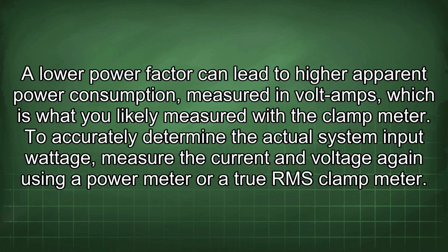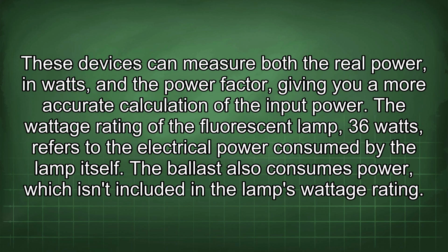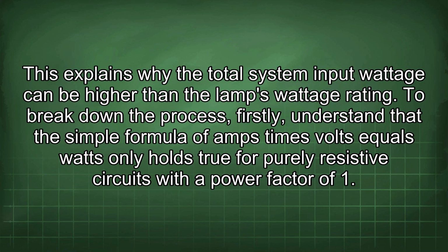To accurately determine the actual system input wattage, measure the current and voltage again using a power meter or a true RMS clamp meter. These devices can measure both the real power, in watts, and the power factor, giving you a more accurate calculation of the input power. The wattage rating of the fluorescent lamp, 36 watts, refers to the electrical power consumed by the lamp itself. The ballast also consumes power, which isn't included in the lamp's wattage rating. This explains why the total system input wattage can be higher than the lamp's wattage rating.